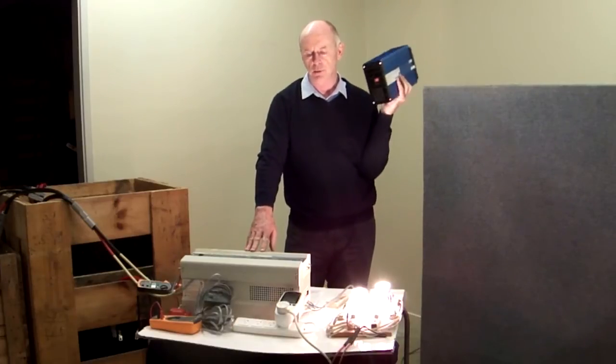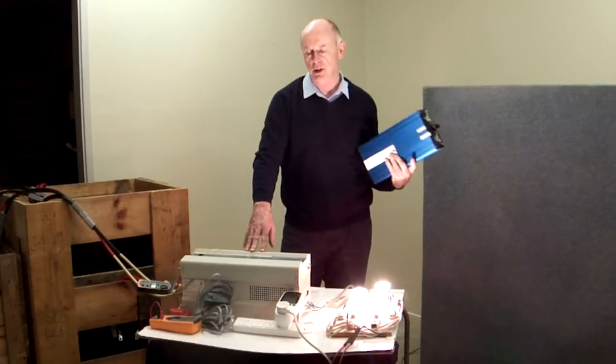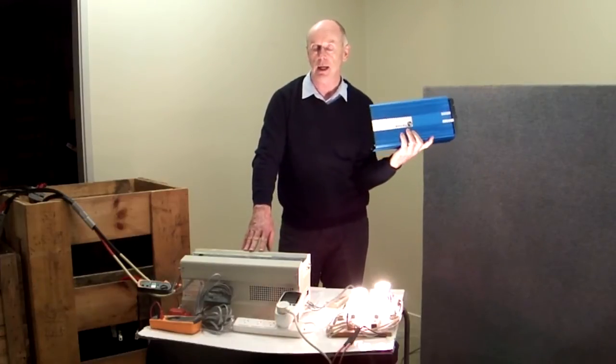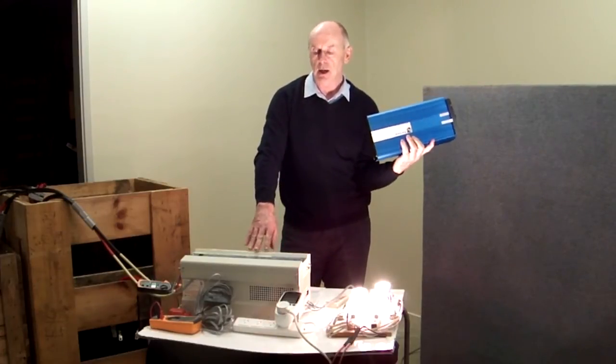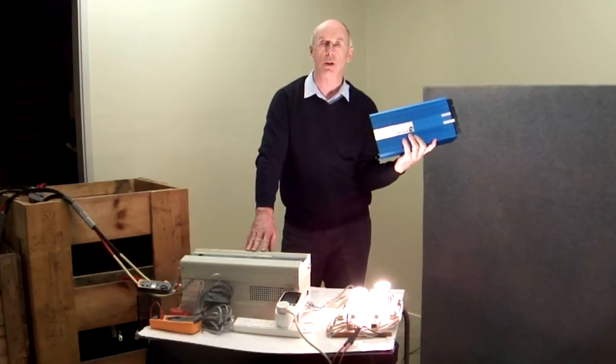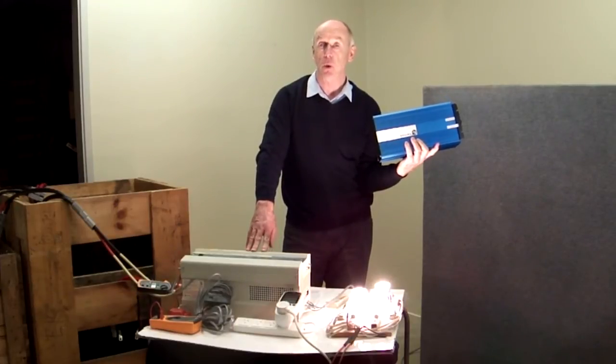This will handle three times rated power, which in this case is a 2,000 watt inverter, 12 volt in, 240 volt out. So it'll handle 6,000 watts for 20 seconds or more.